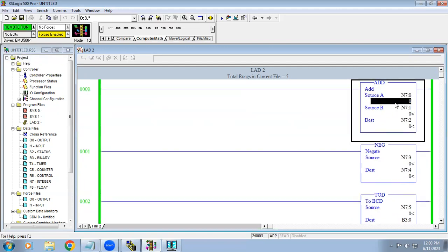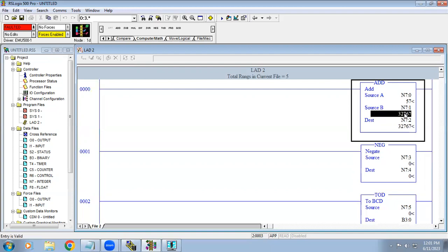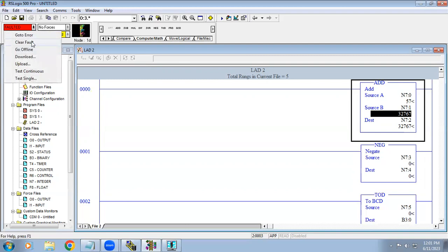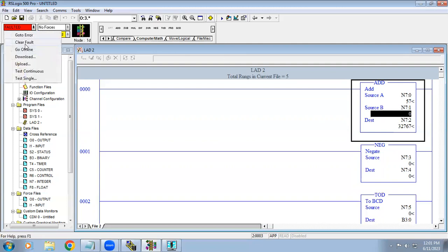In the math function, when I give a value — for example 57 plus 45 — it shows 102. Since we are using integer, we can give minus values as well. The maximum value is 32767. When I type 32767 plus 57, it is out of range, and the controller automatically goes to fault mode. To recover, we have to change the value back to 0 and then clear the fault.